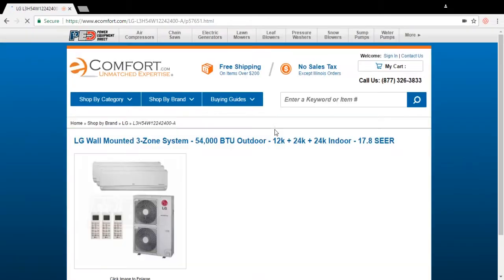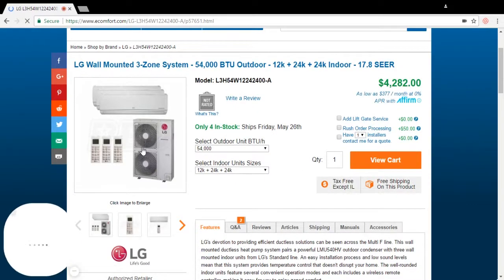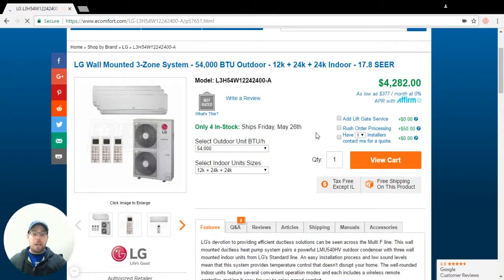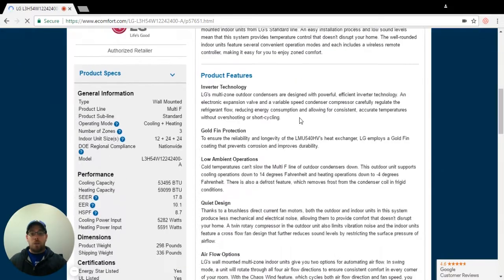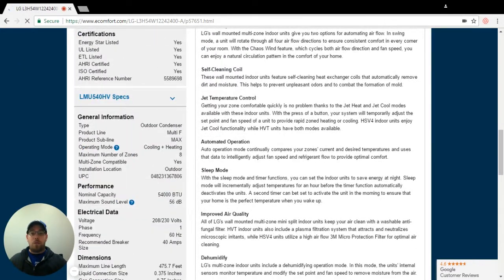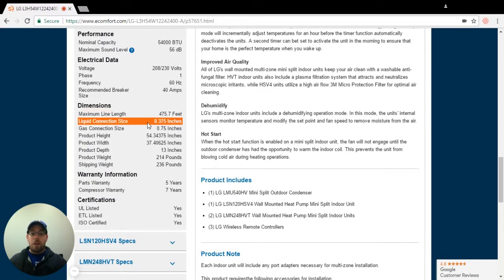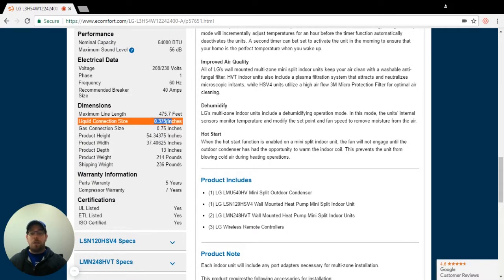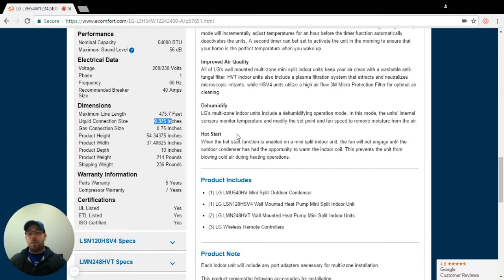Now you need to know the distance between where your compressor is going to be and your branch box. First, I'm going to look up what size lines I need for my branch box. If I remember right, LG is a little off, not meaning bad in any way, but they use a different size line set to the branch box. So that's three eighths by three quarters.